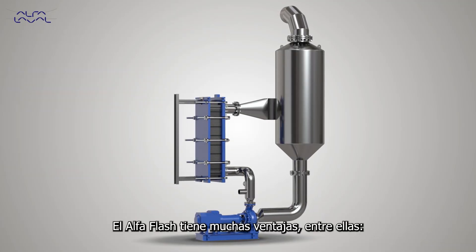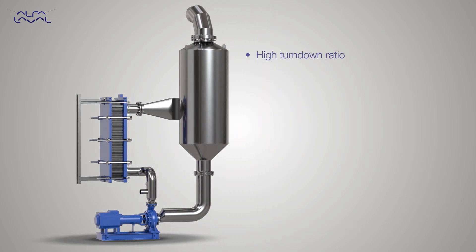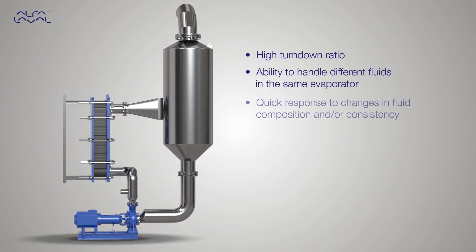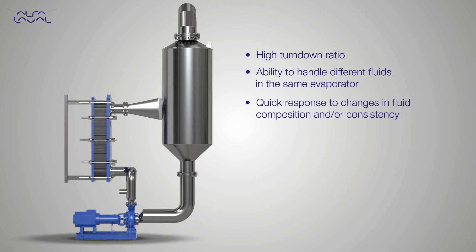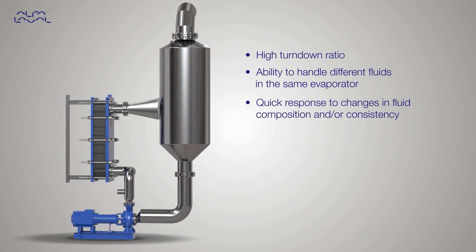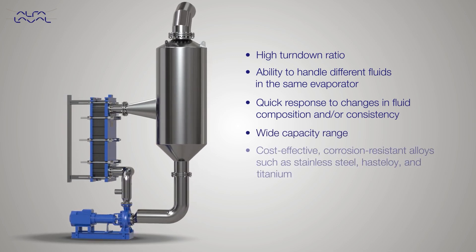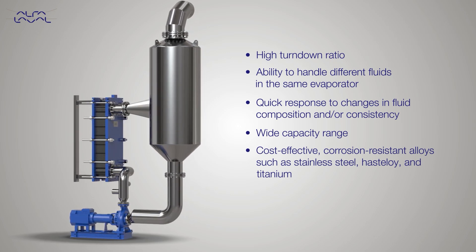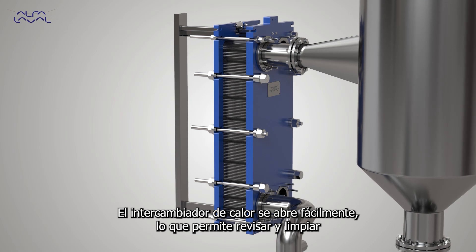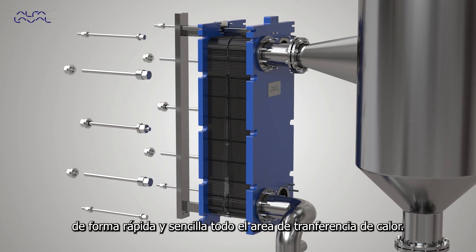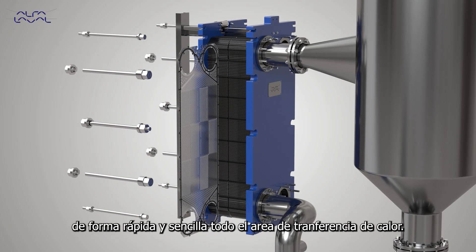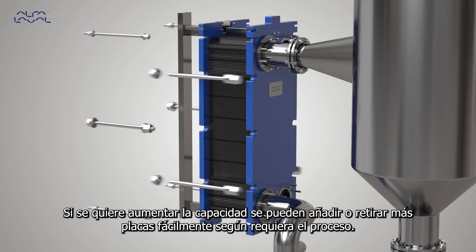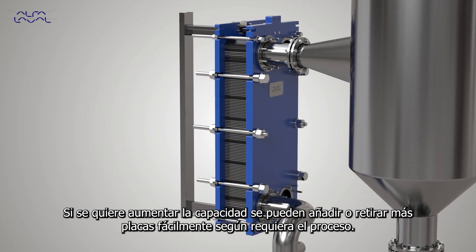The Alfa Flash has many advantages, including high turndown ratio, ability to handle different fluids in the same evaporator, quick response to changes in fluid composition and/or consistency, and wide capacity range. Cost-effective corrosion-resistant alloys such as stainless steel, Hastelloy, and titanium are available. The heat exchanger opens easily, enabling quick, easy inspection and cleaning of all surfaces. To increase capacity or to improve flow characteristics, plates can easily be added or removed according to process requirements.